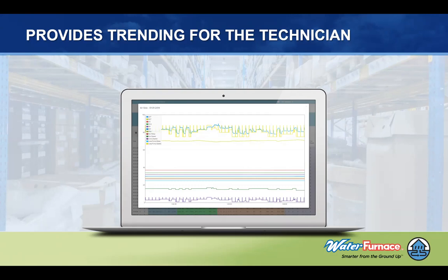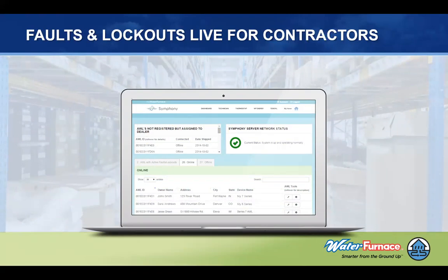It can do water temperature trending, or each of those, and all of the different sensors that we're sensing within the system. It provides lockouts for the contractor so that they know which system has a lockout. So on a home that has 4 systems, you can go right to the system that has the lockout. You can do the troubleshooting on that specific system, and it provides a dashboard for the contractor level to know exactly where you want to look.